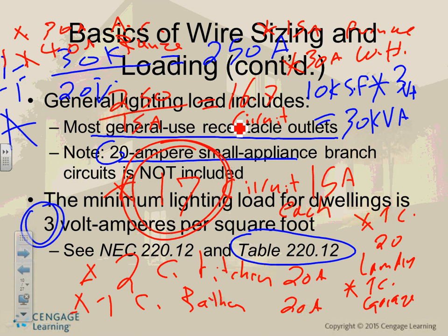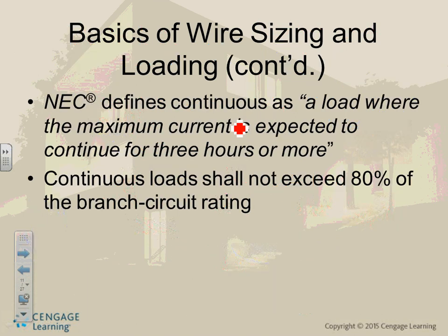So these are all the circuits that you need, guys. We're going to be repeating them over and over as we go through. Okay, so these are your circuits. Continuous load. Do you remember the continuous load? They define the continuous load as 3 hours or more, at full load though. So if you have a machine rated at 100 amp, but it's running at 50 amps for 3 hours, is that continuous load? No. It has to run at 100 amp for 3 hours.